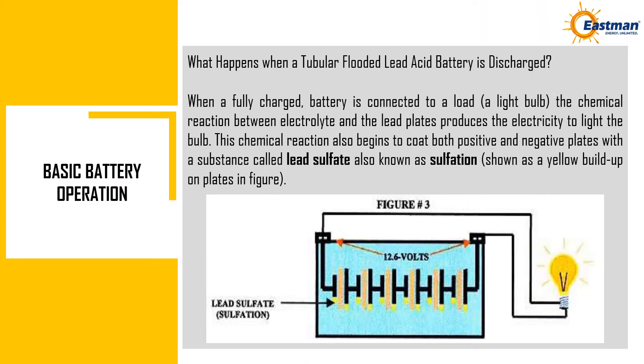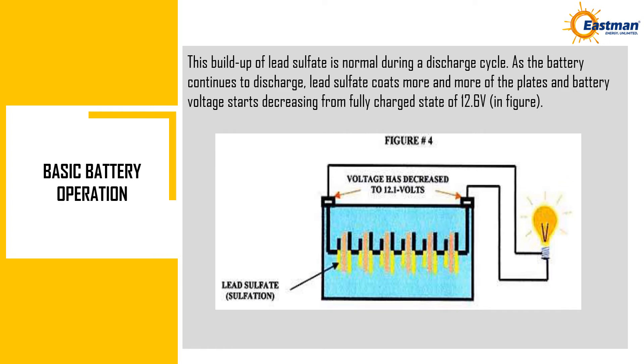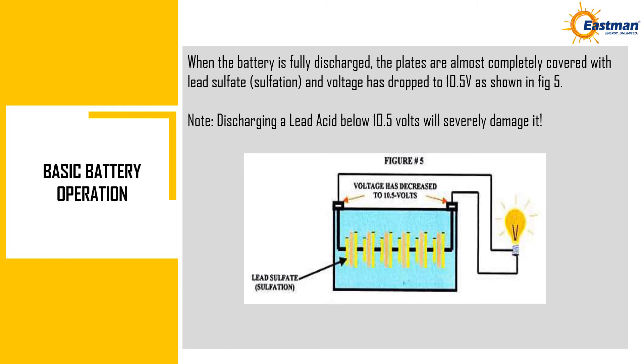Basic Battery Operation. When a fully charged tubular flooded lead acid battery is connected to a load such as a light bulb, the chemical reaction between the electrolyte and the lead plates produces electricity. This reaction also begins to coat both positive and negative plates with lead sulfate, also known as sulfation, shown as a yellow buildup on the plates in the figure. This buildup is normal during a discharge cycle. As the battery continues to discharge, lead sulfate coats more of the plates and battery voltage decreases from the fully charged state of 12.6 volts. When fully discharged, the plates are almost completely covered with lead sulfate and voltage has dropped to 10.5 volts as shown in FIG 5.